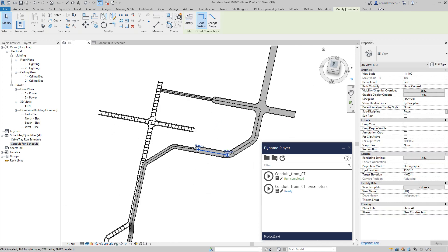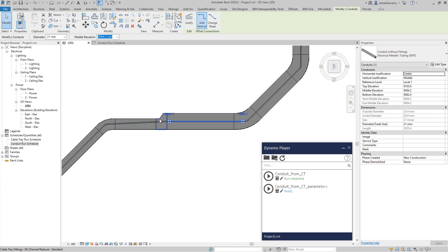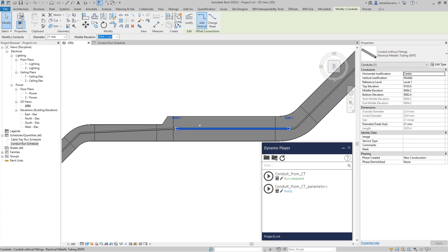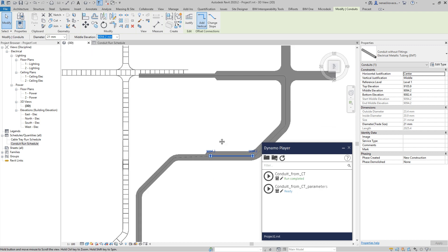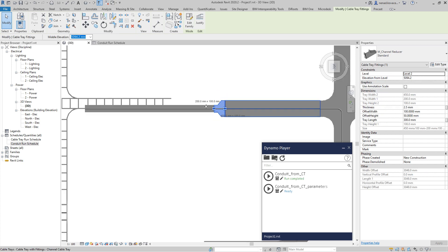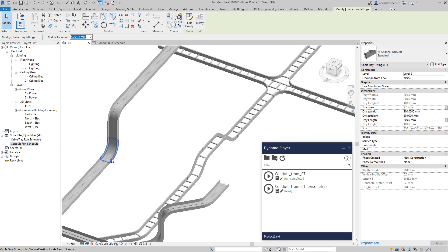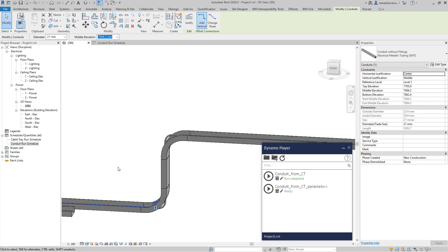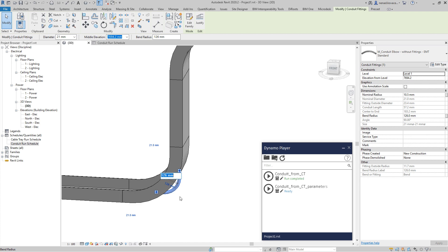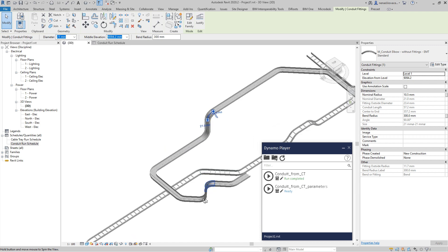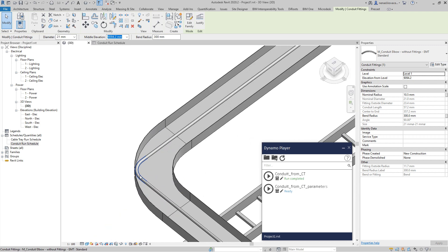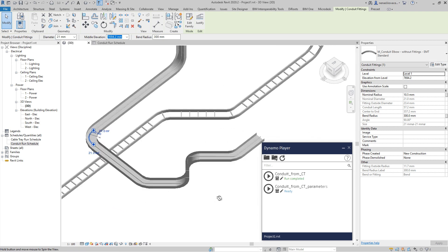Something I need to mention: this situation here with an eccentric reduction. The center of this cable tray is here, but the center point of this fitting is over here. Sometimes when you have those eccentric reductions, you'll have a conduit which tries to follow the centers from each side. When you have a reduction at the center, you won't have those kinds of problems. Also, sometimes following this route, the bend radius will create some clashes. But you can go manually and change the bend radius where necessary, or you can select all conduits and change all elbows — for example, the same thing over here — changing that radius.